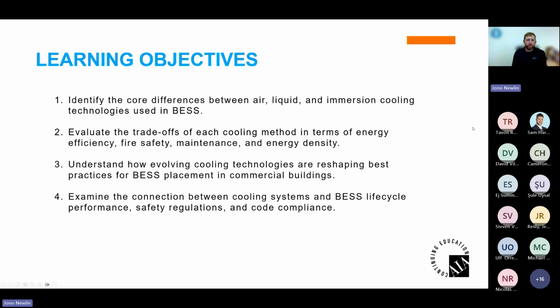So again, I want to re-emphasize the learning objectives. We identified the core differences between air-cooled, liquid-cooled, and immersion-cooled in BESS use cases. How are we taking that to our projects? We're looking at, is it NMC, is it LFP, what chemistry is needed here? That might be basic knowledge for you, but it's key for performance on the cooling side. And then what type of cooling does it have: air-cooled, liquid-cooled, or immersion-cooled? What type of job am I doing?